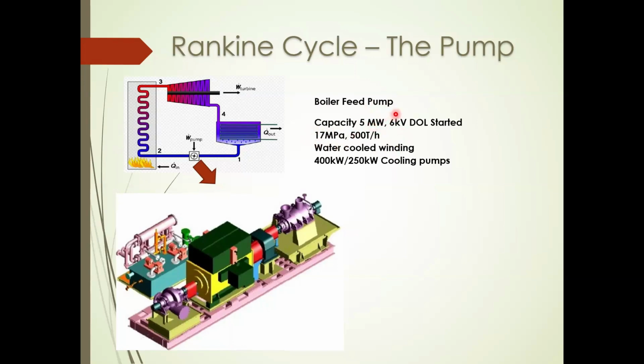at a pressure of 17 megapascals. Since it's quite large, it's a major equipment in the power plant, supplied by the 6 kV auxiliary station supply. Since the pump is quite large, the assembly of the pump and the motor is quite heavy. So, your bearings need to be lubricated properly, and the lubrication has to be cooled properly. So, we have a separate lubrication oil station.